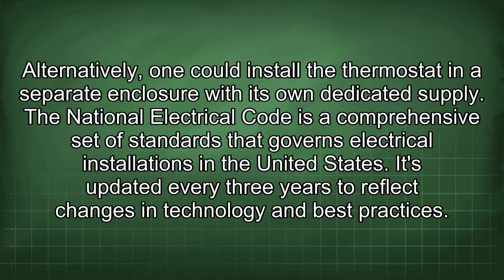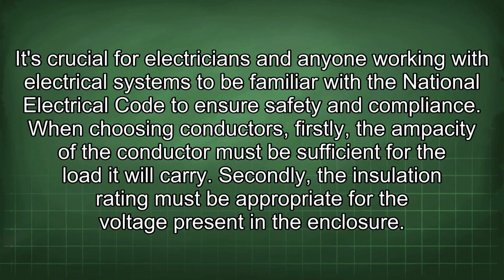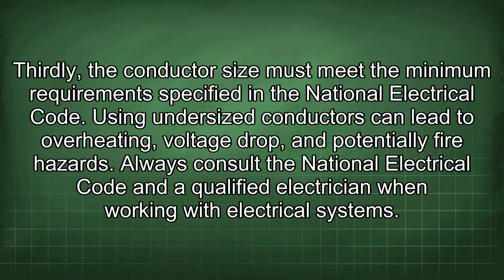The National Electrical Code is a comprehensive set of standards that governs electrical installations in the United States. It's updated every 3 years to reflect changes in technology and best practices. It's crucial for electricians and anyone working with electrical systems to be familiar with the National Electrical Code to ensure safety and compliance. When choosing conductors, firstly, the ampacity of the conductor must be sufficient for the load it will carry. Secondly, the insulation rating must be appropriate for the voltage present in the enclosure. Thirdly, the conductor size must meet the minimum requirements specified in the National Electrical Code.